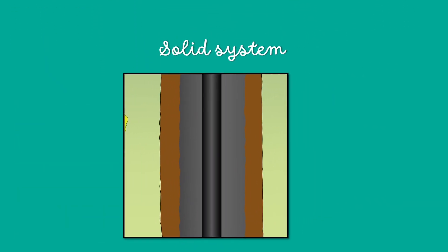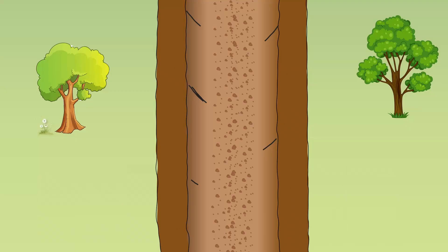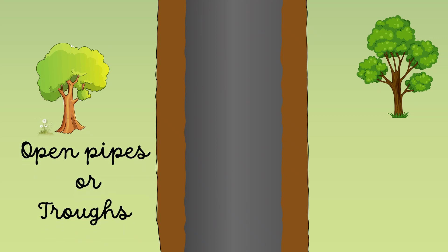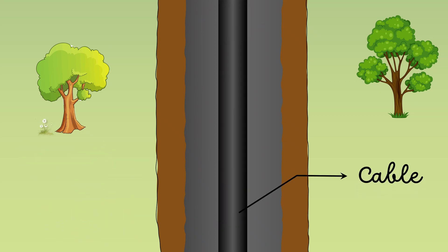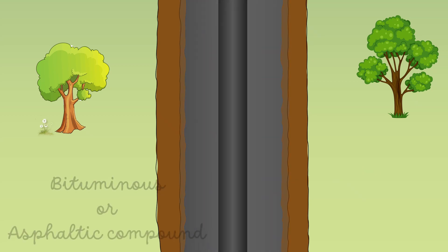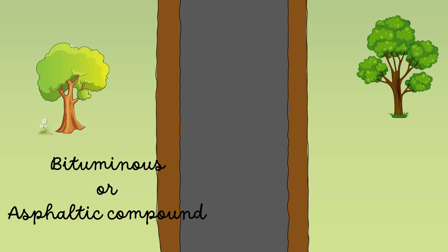Now let's get to a solid system. In this method of laying, the cable is laid in open pipes or troughs dug out in the earth along the cable route. After the cable is laid in position, the troughing is filled with a bituminous or asphaltic compound and covered over.